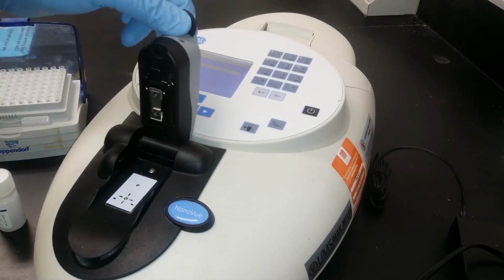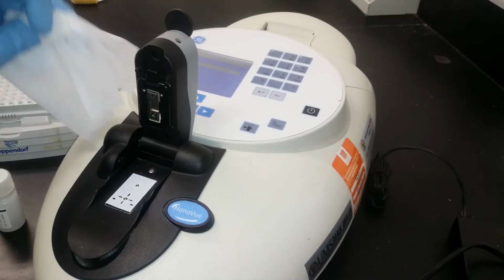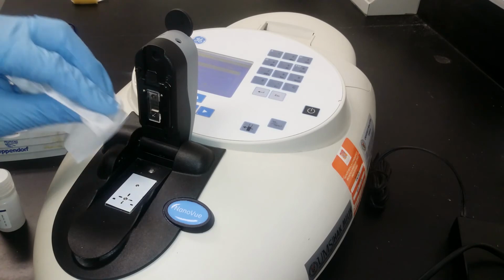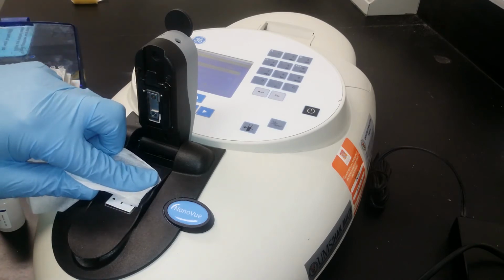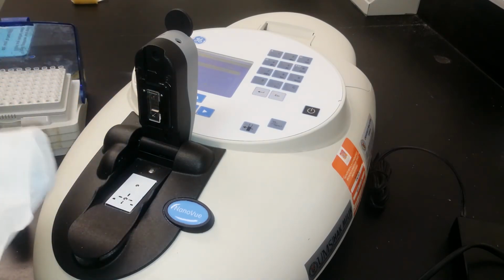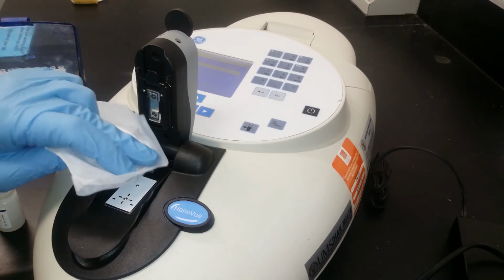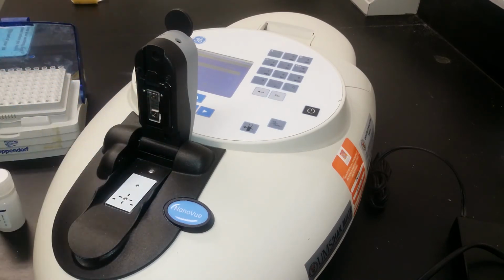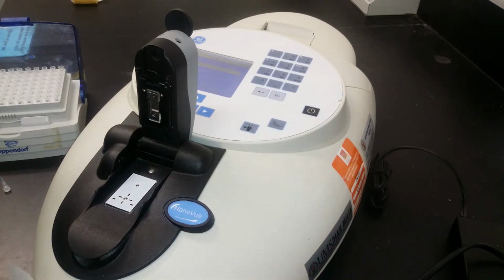You will need to do this operation twice in order to calibrate the instrument. So when you wipe off the instrument, ensure that you use Kim wipes and move in this manner. So I will repeat this procedure with another 2 microliters of the solution.